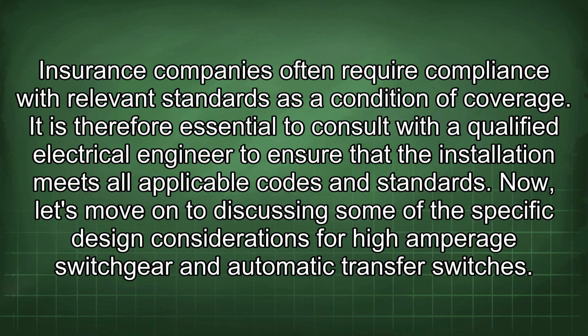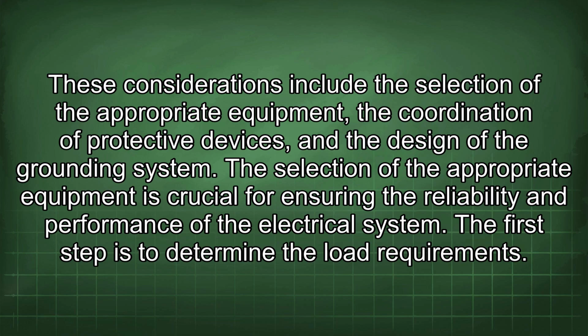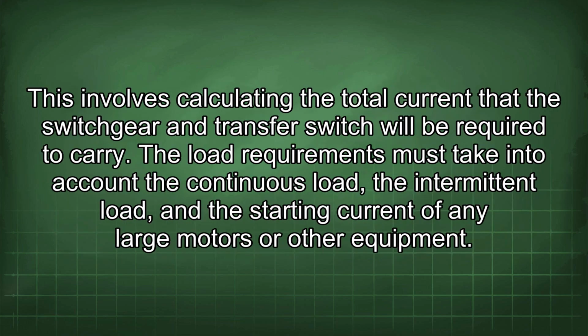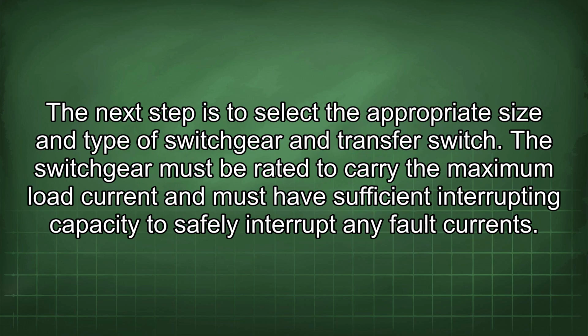Now, let's move on to discussing some of the specific design considerations for high amperage switchgear and automatic transfer switches. These considerations include the selection of the appropriate equipment, the coordination of protective devices, and the design of the grounding system. The selection of the appropriate equipment is crucial for ensuring the reliability and performance of the electrical system. The first step is to determine the load requirements. This involves calculating the total current the switchgear and transfer switch will be required to carry. The load requirements must take into account the continuous load, the intermittent load, and the starting current of any large motors or other equipment.